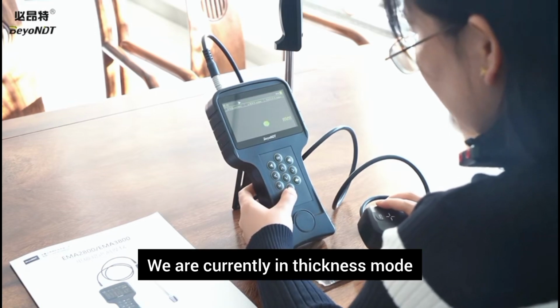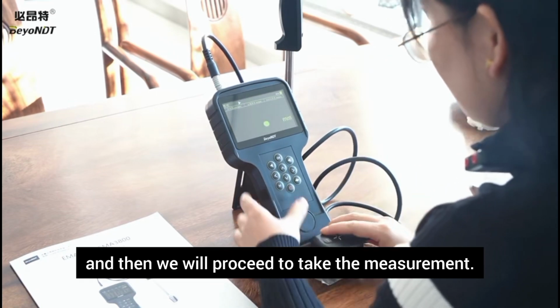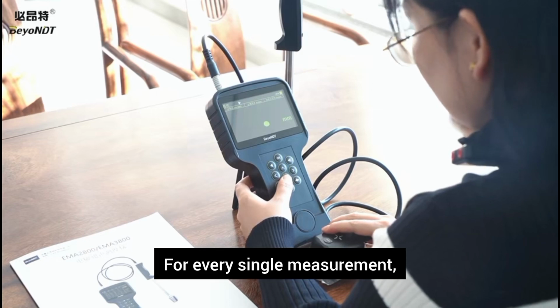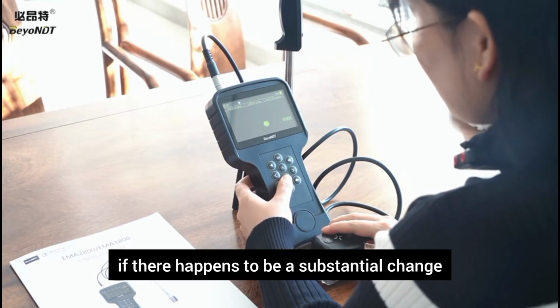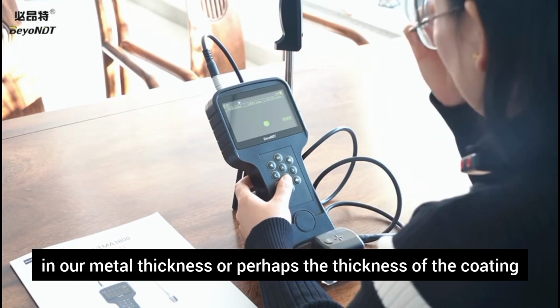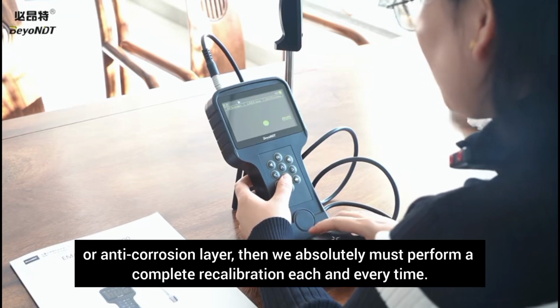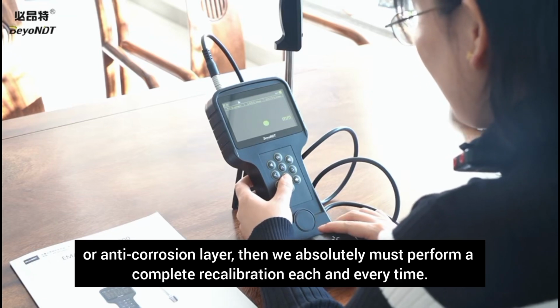We are currently in thickness mode, and then we will proceed to take the measurement. For every measurement, if there happens to be a substantial change in our metal thickness or perhaps the thickness of the coating or anti-corrosion layer, then we must perform a complete recalibration each and every time.